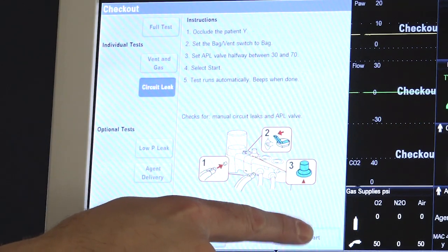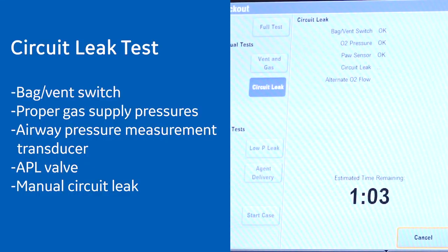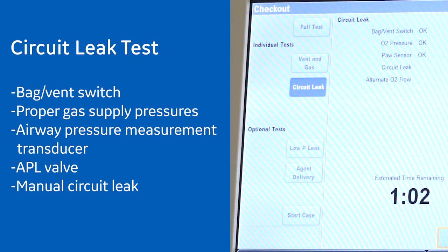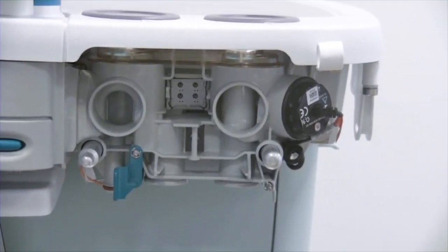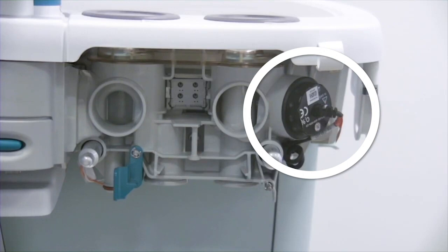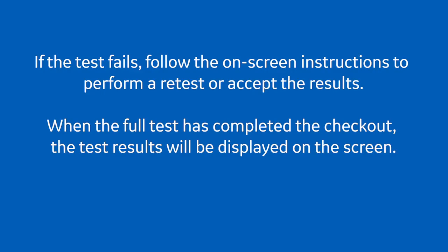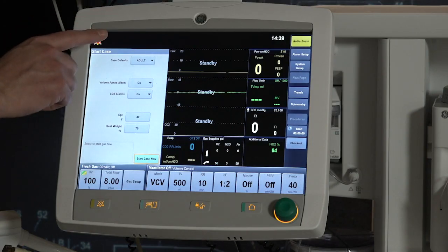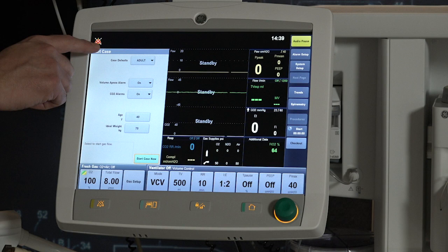The circuit leak test checks the bag to vent switch, proper gas supply pressures, airway pressure measurement transducer, APL valve, and manual circuit leak. Perform a check on the O2 cell if there is no integrated gas module. Press Start Case to open the Start Case menu. Use the Start Case menu to set the case data and start the gas flow.